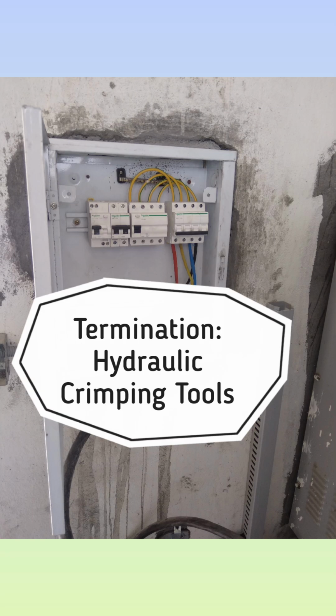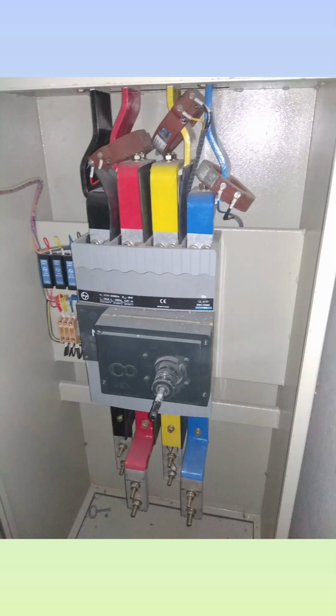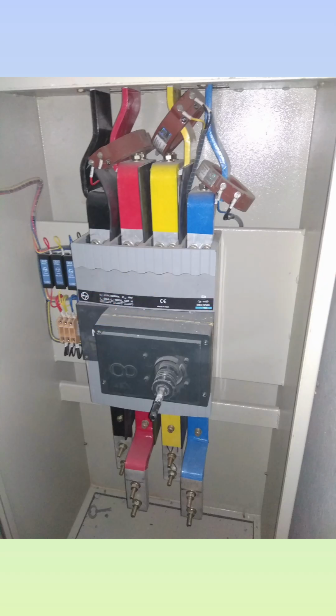For termination, we use hydraulic crimping tools with hexagonal dies. This ensures a cold weld connection. All lugs are torqued to the manufacturer specified value. For an 800 ampere MCCB, the torque is 20 Newton meter, verified with a calibrated torque wrench.